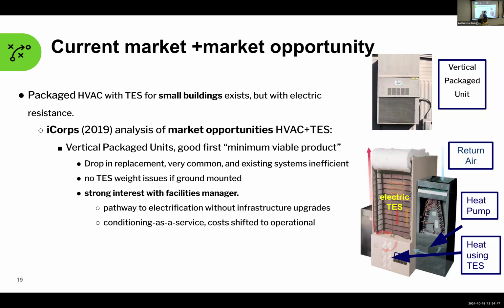Yeah, that is what it does. It provides that additional capacity. I'm not in the business of selling these systems currently, so I don't face that challenge, but you're exactly right, this is the point we're trying to make: by combining the two together, it's an enabling technology. It allows you to use heat pumps in situations where the electrical need would otherwise be too large, requiring an expensive oversized heat pump. It also helps where people might be concerned about the capacity they can get out of the heat pump, because you can say, look, you run the heat pump all day, charge up the thermal energy, and then draw upon it when you need that capacity. It is challenging to make that argument.